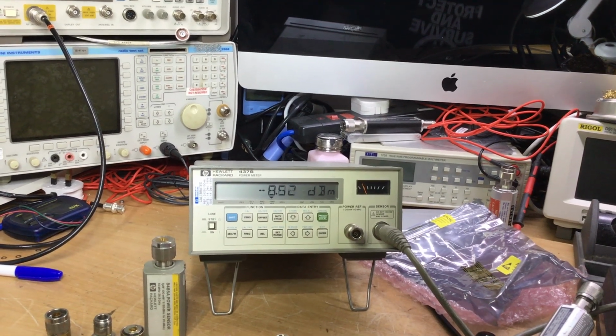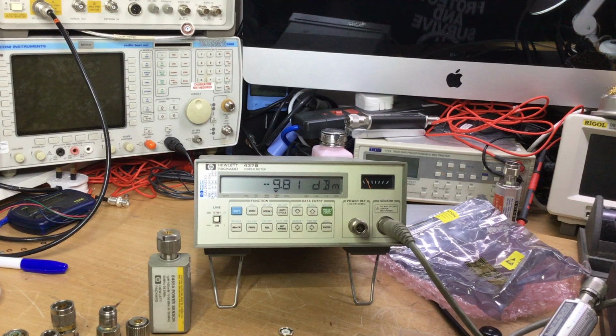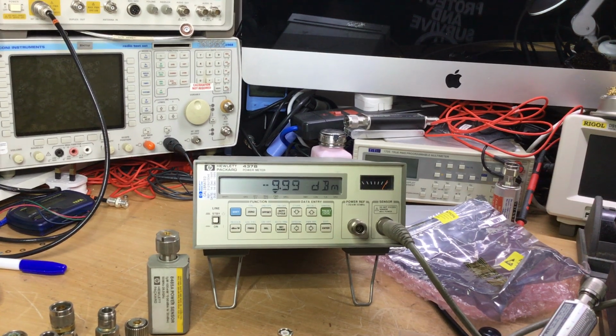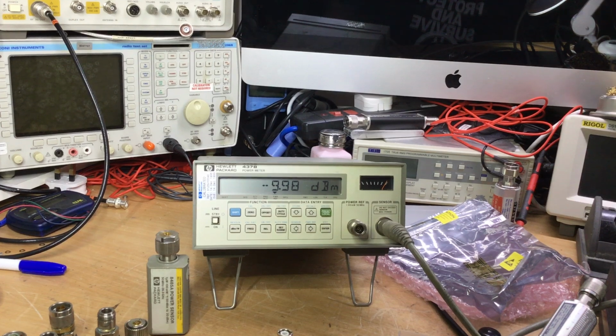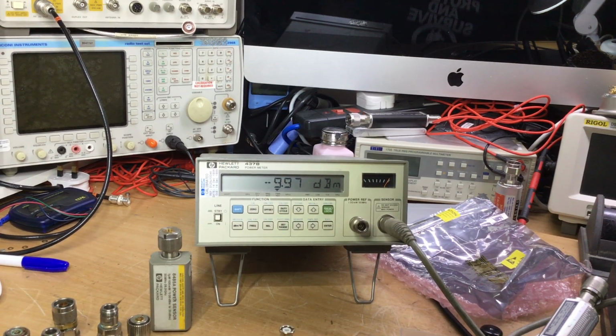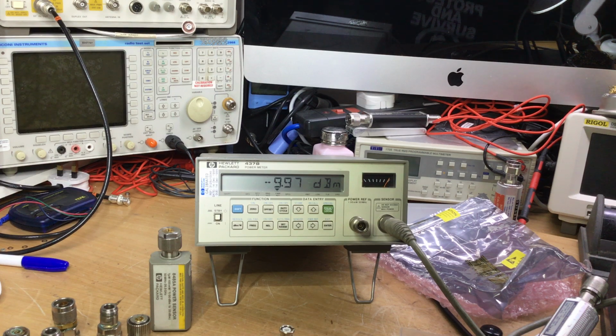And right, so let's have a look here. So that would be, as it reads on the Marconi, minus 10 dBm, right up to 26.5 gigahertz. So as you can see there, it's quite accurate. You know, it's just 0.1, 0.2 of a dB, possibly 0.3 at the most of a dB off. In this case, obviously, because the meter's reading slightly, well, its output slightly out on the reference, but it proves the sensor's reading fine without problem.